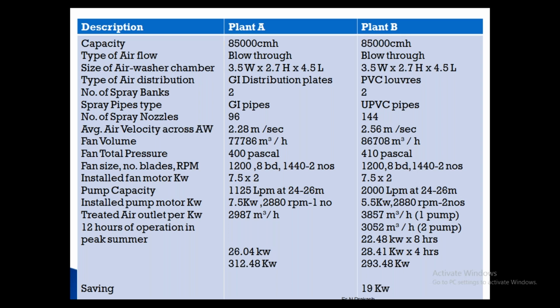The size of the air washer chamber: width is 3,500 mm, height is 2,700 mm, and the length of the chamber is 4.5 meters. The chamber length is important because the air and water mix, and that needs some time to travel. Then only will the spray efficiency increase. So that is the length of the chamber, and then the type of air distribution.